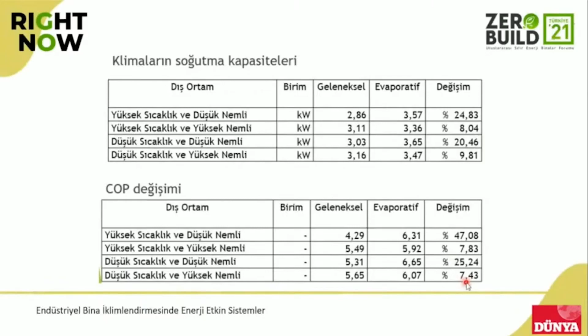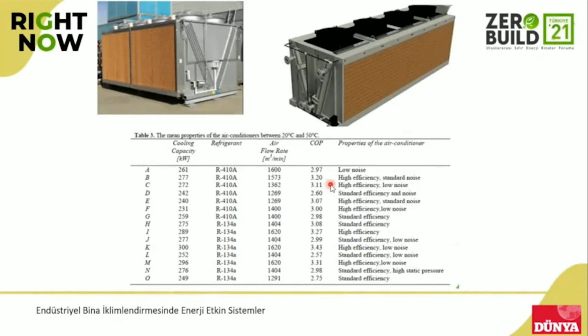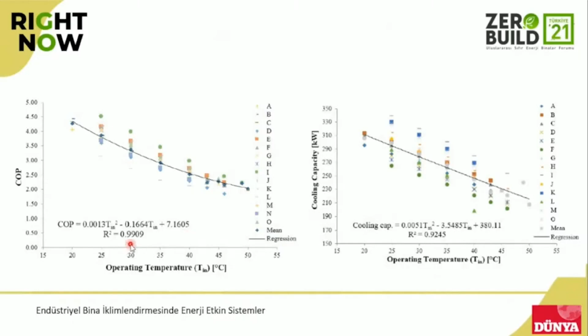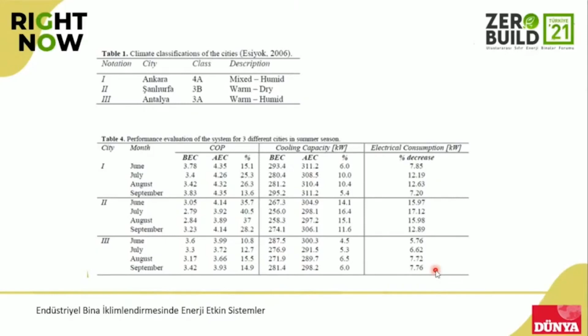Here we use chillers. If you have air condensing ones with evaporative pads behind, our simulations on many chillers show that cooling capacity changes depending on outside temperature, along with COP. With high regression numbers, we saw that in climates like Urfa, energy consumption decreases up to 15%. In Ankara it's 7%, and in Antalya around 5.8%. So this is an alternative, energy efficient system for industrial buildings.